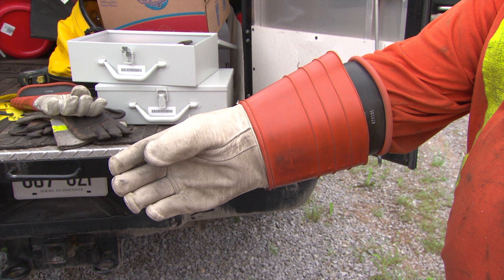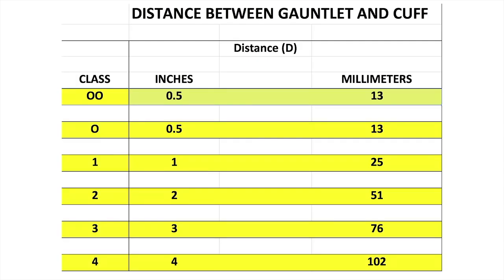When covers are on the gloves, the rubber glove cuff must be visible above the glove cover for the prescribed amount according to the class of gloves. The rule of thumb is 1 inch of glove showing above the cover per 10 kV of test voltage and ½ an inch for any glove tested below 10 kV. A thorough inspection of selected gloves must be performed prior to use.